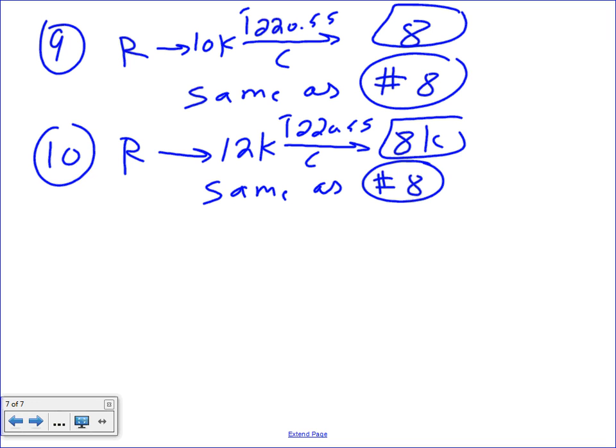Why did I put 6? The question then would be, why the heck did you put 6, Chad? Because it's going to make a major difference when we size the feeders. It doesn't play any role in the branch circuit. Okay, good point though. Let's do number 11.